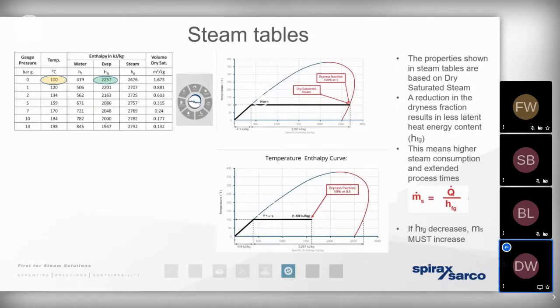As we've mentioned previously, the steam tables that are demonstrated up in the top left-hand side of the screen are based on the understanding that that steam is perfectly dry and free of air and other non-condensable gases. And for reasons we've gone through previously, it's nigh on impossible to guarantee that that steam will arrive at the process 100% dry. But if we use the example of really not being on top of how we're controlling the steam in the boiler house, if we're not observing good working practice with how we distribute the steam, then it's inevitable that we could have an excess of moisture or a very poor dryness fraction.